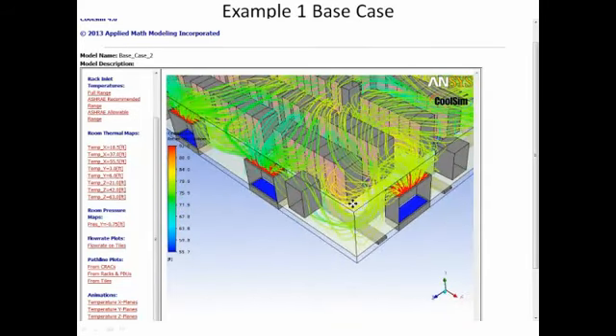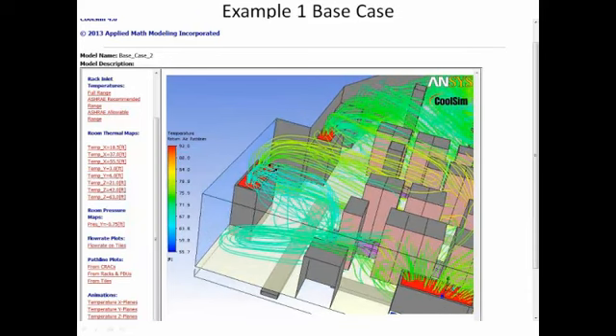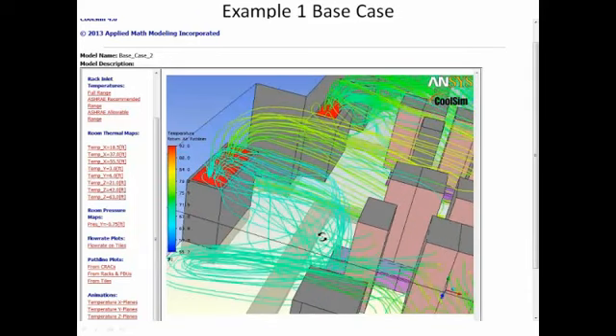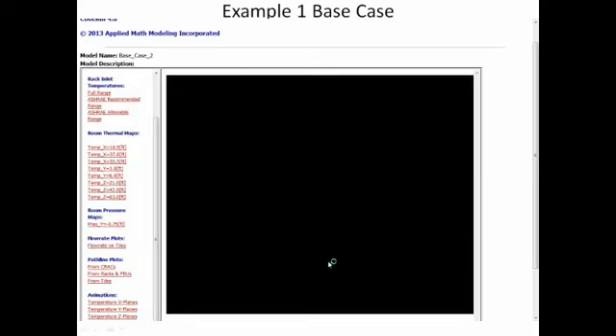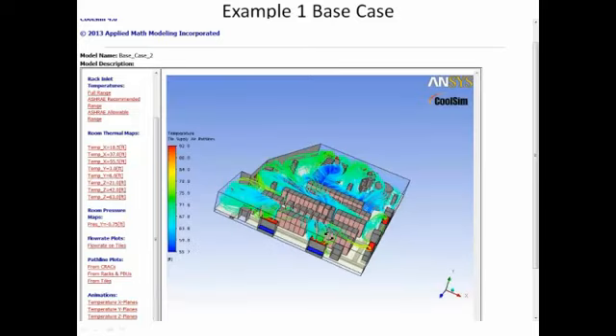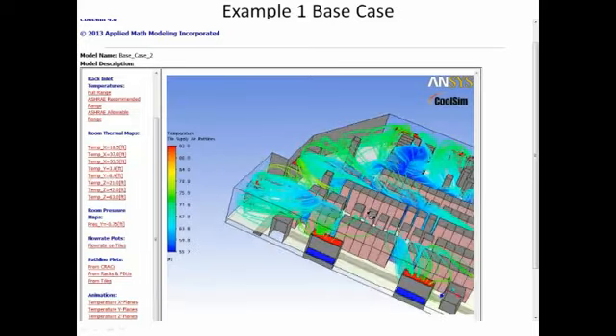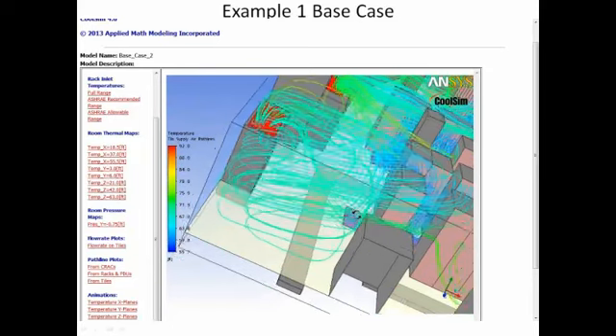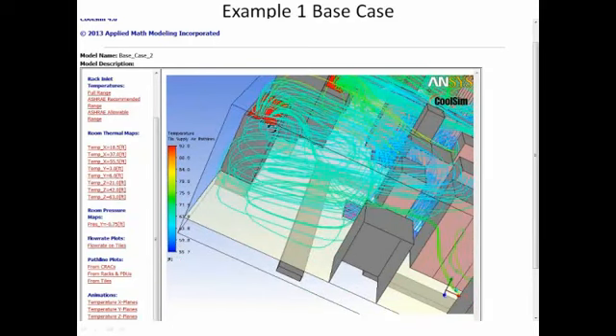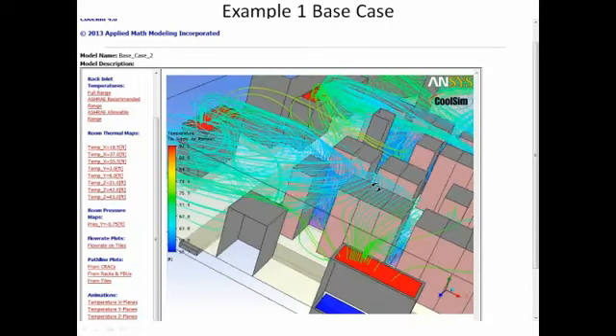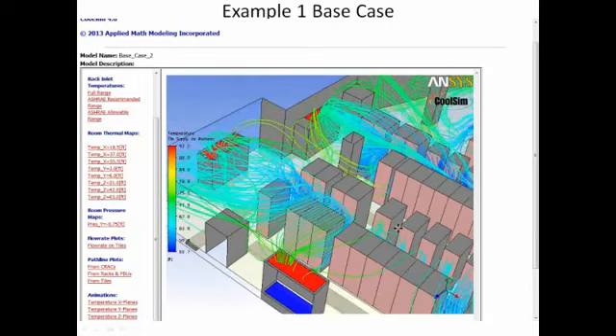We're familiar with this. The other thing I wanted to point out here, Magnus, is the bypass over here. This is the CRAC that's not doing much work, and you can see why. There's air coming right back around on the return. Let me show you the supply. Here's the supply side here, and look what's going on. It's coming right out of the tiles and right back to the intake. So we've got recirculation occurring here where it comes out of the tiles and goes around in a circle, not doing any cooling there, Magnus. And that's why we only have a 12-degree delta T on that unit.